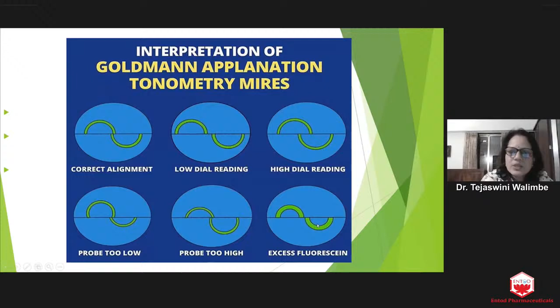So wider menisci cause falsely higher pressure estimates. Then this Goldmann applanation tonometer, all calculations are based considering a central corneal thickness of 520 micron. So depending on the CCT, we may get a false reading. Like in corneal edema, we may get a higher reading: thick cornea, high reading; thin cornea, low reading. Post-refractive surgery, sometimes less intraocular pressure is recorded. So we have to be careful and consider the central corneal thickness.